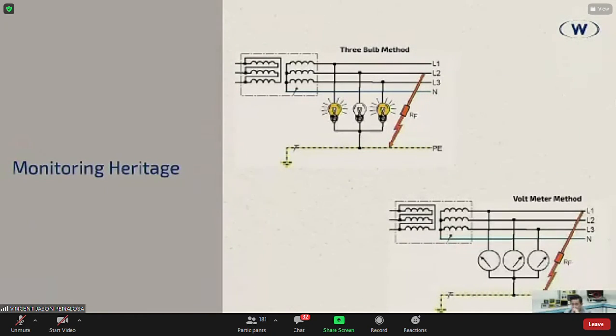So since it was a mining facility, it was an ungrounded system. So they connected bulbs, line to ground. And then, whichever bulb actually flickers or lumalabo or even namamatay, they know for a fact which phase is actually having a problem, no? So that's great. Somehow it's effective, no? And then, of course, with the same concept, you can use the voltmeter method. So, if you have your regular power energy meter, right? If you had your regular power energy meter and you connected it and it's on a delta, then one of your lines drops down, and then you measure voltage on your ground, you know for a fact that that particular phase is actually the one with the fault, right?